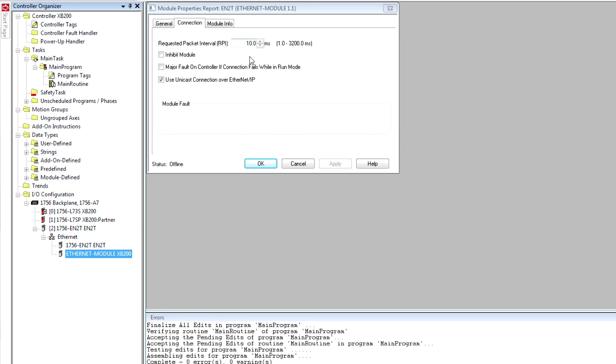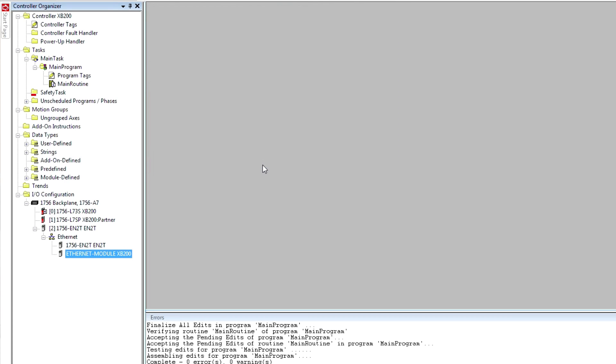The minimum RPI supported by the XB200 is 20 milliseconds, so that has to be changed from the default of 10. And that's sufficient to establish communication between the XB200 and the ControlLogix.